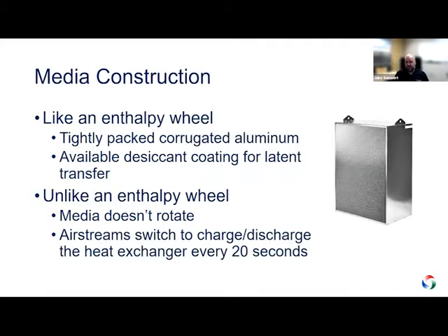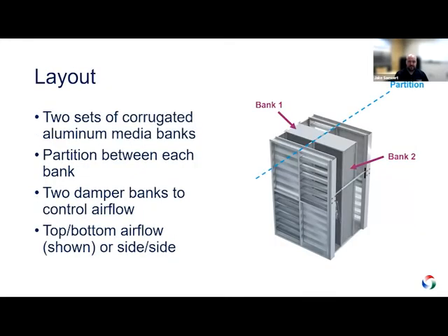However, unlike an enthalpy wheel, the media doesn't rotate, it's fixed in place. What we're going to end up doing is, instead of rotating the media, we're changing the airflow over a 20-second cycle. So we'll essentially charge the media for 20 seconds, and then the airflow will reverse through it and discharge the energy that we put into it. So it's changing the airflow through the static media instead of rotating like a wheel would.